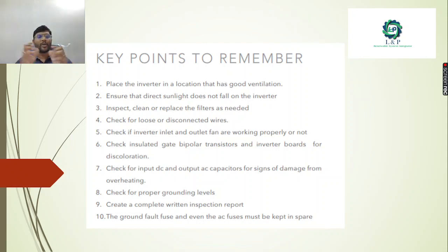Okay, and the key point you need to remember is to always look for a place for the inverter that has good ventilation, and make sure no direct sunlight falls on your inverters, while the sunlight falls on your solar PV modules. Inspect, clean, and replace the filters of the inverters. Check for loose and disconnected wires. Check if the inverter inlet and outlet fans are working properly.